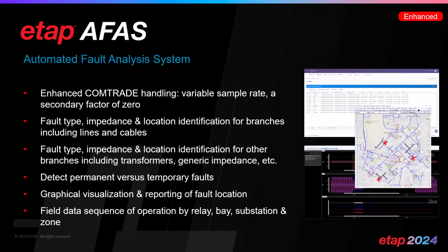We've also enhanced our AFAS solution, our automated fault analysis system, by improving ComTrade handling with a better variable sample rate and better fault type and impedance type identification—for branches that include lines and combinations of cables, as well as branches that include transformers. This means identifying the fault type for a complex branch made up of lines, cables, and transformers.